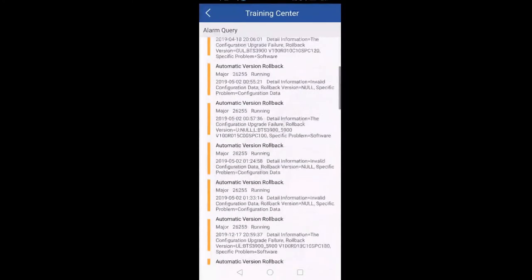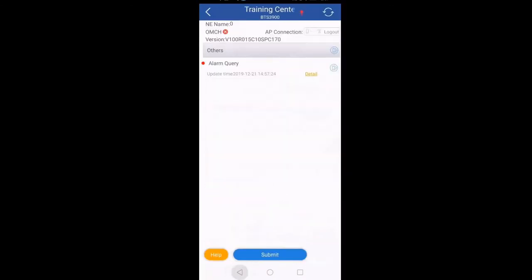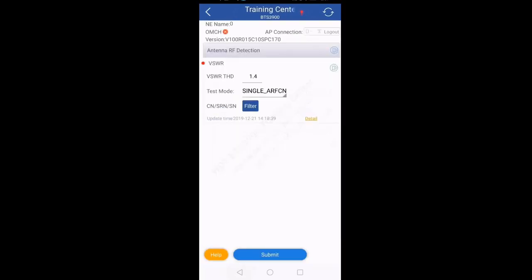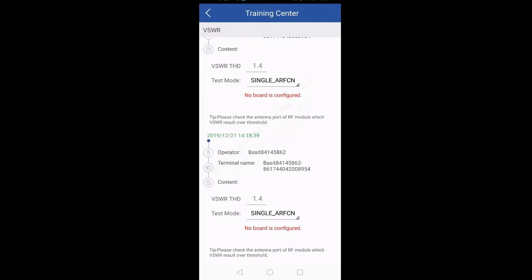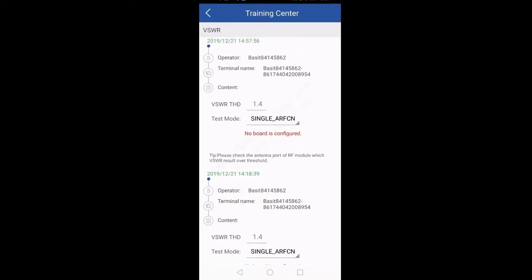If you want to check VSWR values, go to the fourth option: Antenna RF Detection. Set the value threshold — currently it is 1.4. Click on the play button, and when you click on Detail it will give you all the VSWR values on different jumpers. Since here in the training center we don't have any RRU configured, it is showing no board is configured. But on site it will give you all the VSWR values for different jumpers and different RF ports.